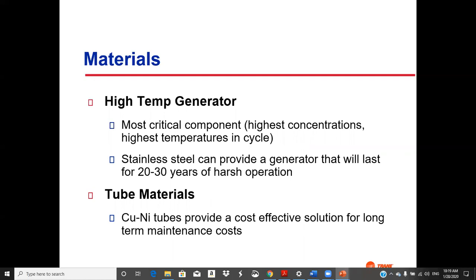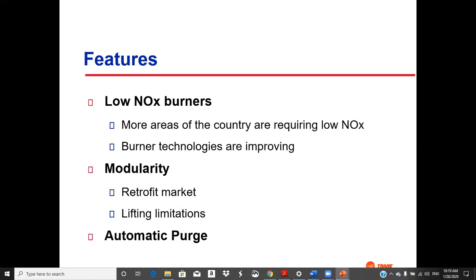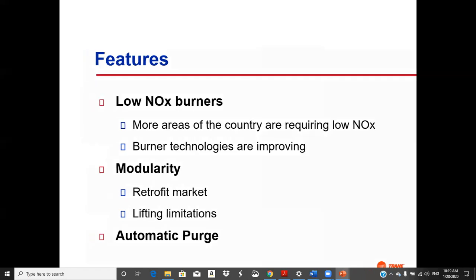So in the materials, the generator sees the highest temperatures and concentrations. So stainless steel, that's one reason it's expensive. Stainless steel is not cheap. And then tube materials have been improved. Low NOx burners on the direct fired to reduce NOx emissions. Modularity, automatic purge to get the air out of the system.